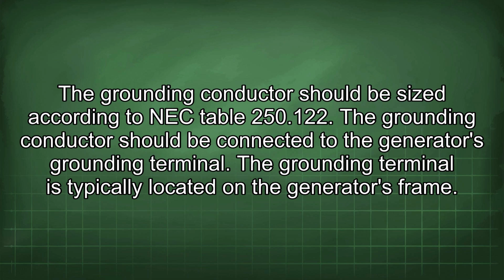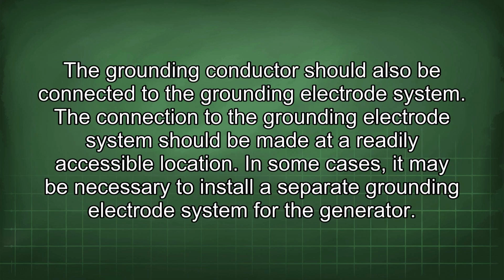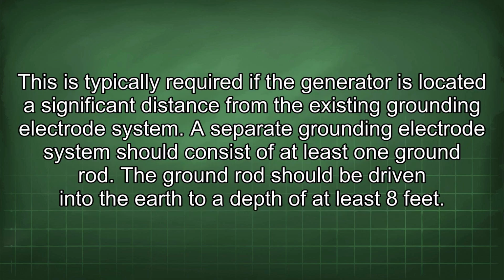The grounding terminal is typically located on the generator's frame. The grounding conductor should also be connected to the grounding electrode system. The connection to the grounding electrode system should be made at a readily accessible location. In some cases, it may be necessary to install a separate grounding electrode system for the generator. This is typically required if the generator is located a significant distance from the existing grounding electrode system.